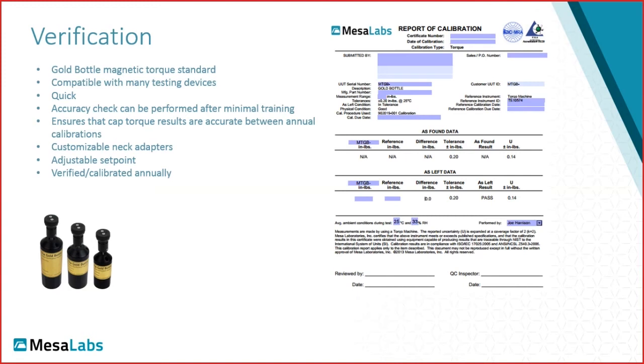So this is probably even more interesting. It's equally interesting and important as the calibration. But what I really like about verification is that it does not require a trained operator. The operator can just place the gold bottle on the platform of the torque tester and start the test cycle, and the machine will measure the magnetic breakaway torque of that gold bottle, displayed on the screen. And if that measurement does not match the set point on the gold bottle that we calibrate in the factory, then you know that something happened to the torque tester, and it should be either recalibrated or serviced, because there may be a problem with the strain gauge.